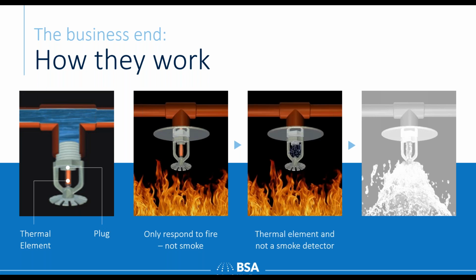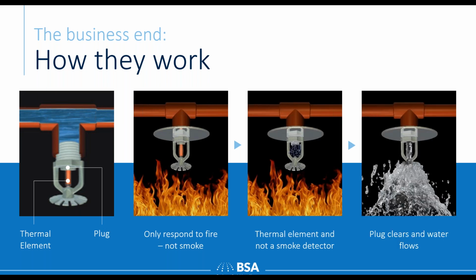And then you start off the chain of events which sees the plug is ejected by the pressurized water, and then we get the water flow. The key thing to point out here, there are no wires attached to this. It's not about smoke. It's all to do with temperature and the heat that's generated from the fire that sets the sprinkler off. That's why all these stories you hear about people having a crafty cigarette or burning their toast, they will not set off a sprinkler system.